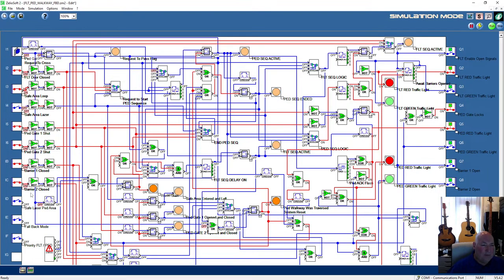Right, so I can easily swap that output for this one and feed it back into this system, but they need to come down here. These inverters need to come down here. And we need to work out something with that one. We're going to change the logic. Then, also, while doing that, we've also got to work out a fallback mode. Now, that fallback mode has got to override the system logic.